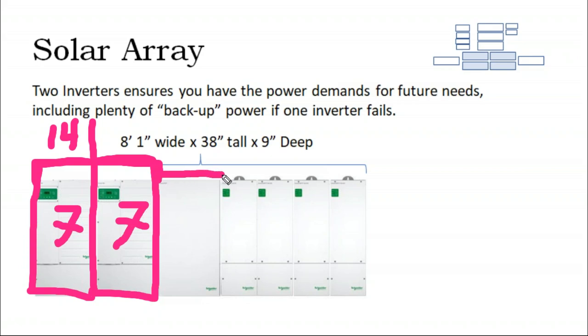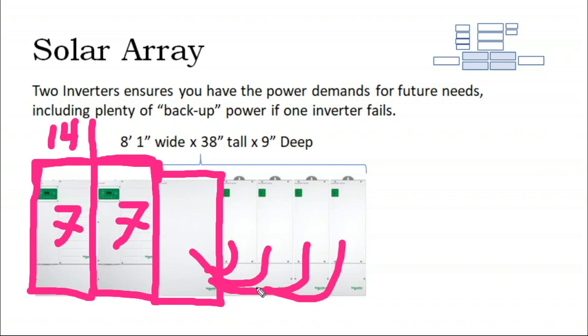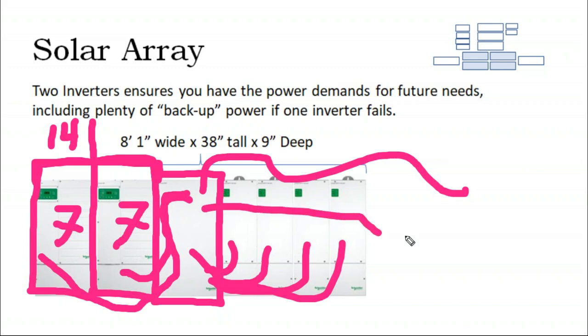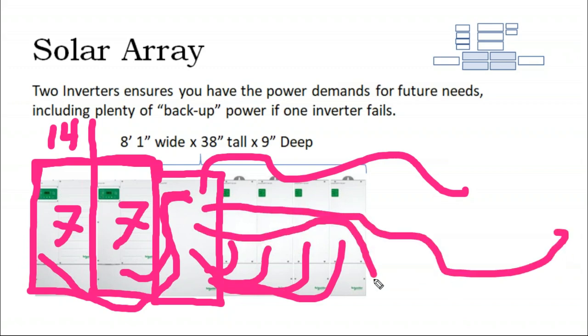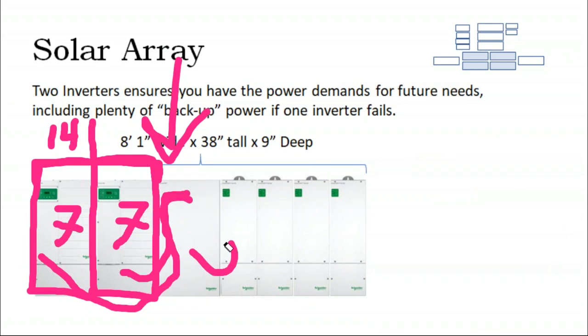You know, now you need a special service panel, because this service panel is the one where it's taking the DC side from the charge controllers and then the AC side from the double stacked inverters and then out to the grid and then out to the generator and then out to the critical load panel. So this is a special service panel that is in addition to the electric service panel.